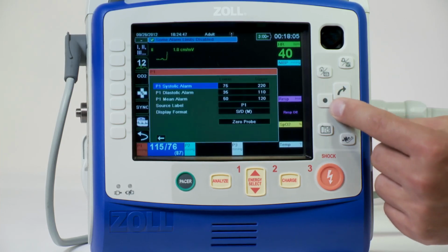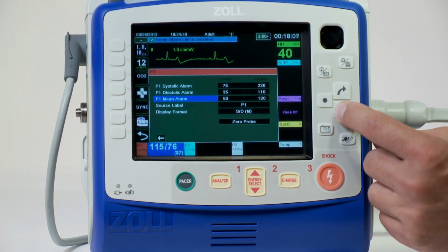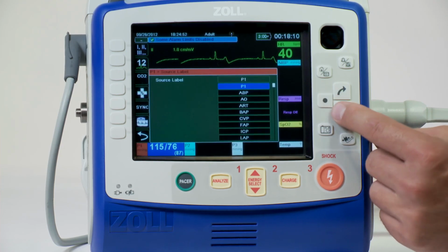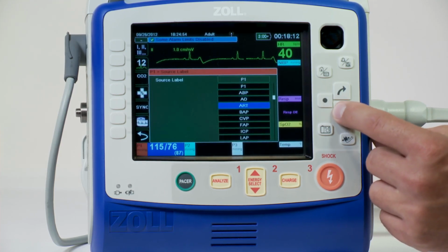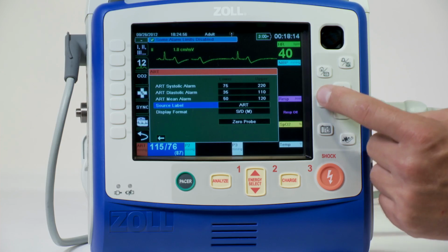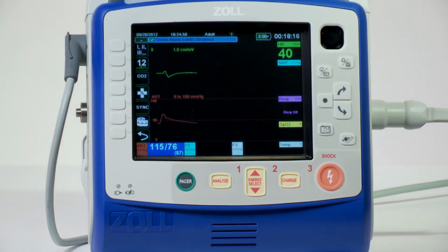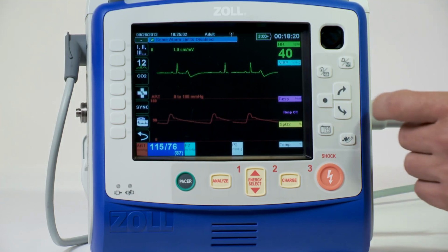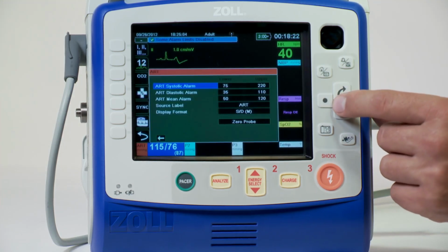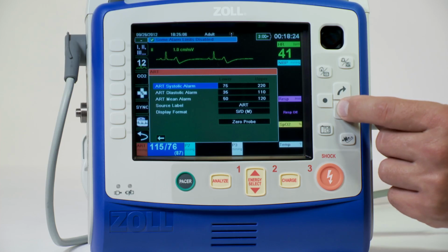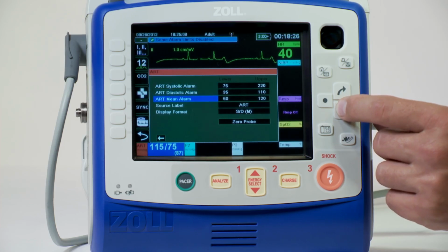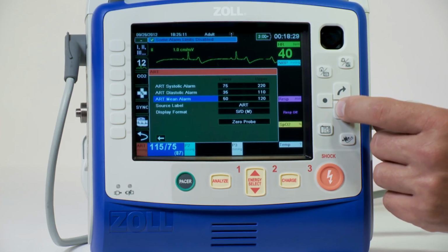To set the IBP source label, you will need to go to the IBP channel menu and select a label that identifies the source of the channel's IBP measurement. By default, the channels are labeled P1, P2, and P3. You have the option to enable, disable, and set the IBP alarm limits. Enable or disable IBP alarms. Set upper and lower alarm limits for systolic, diastolic, and mean arterial pressure values.